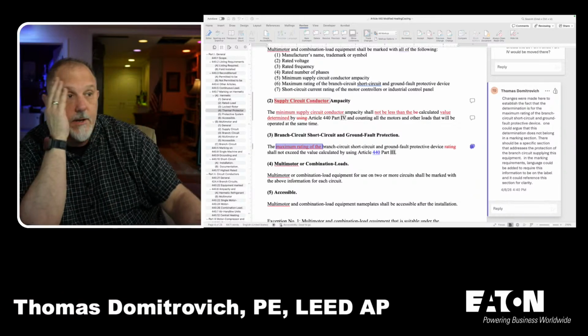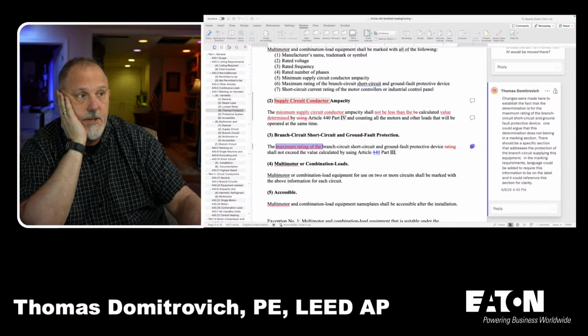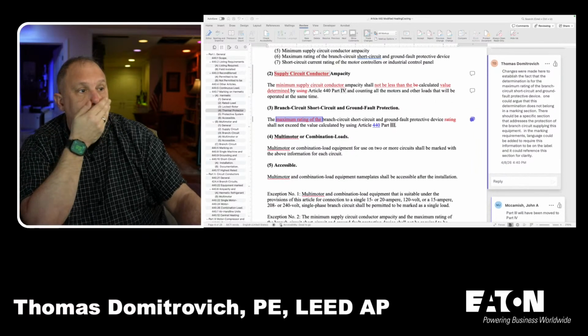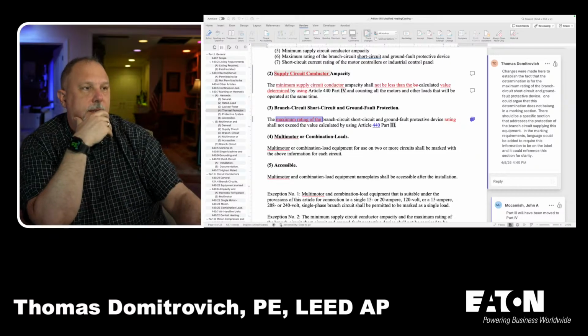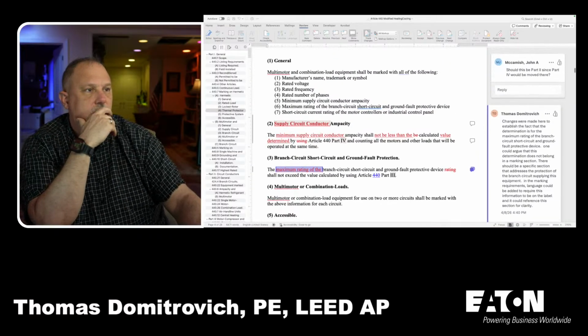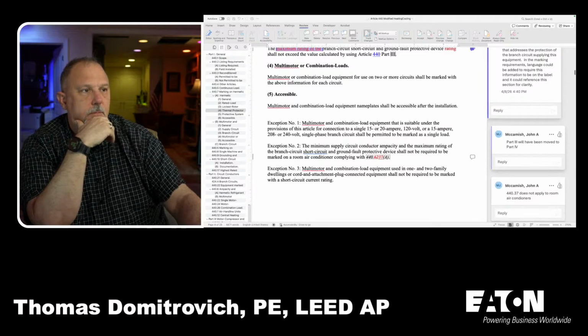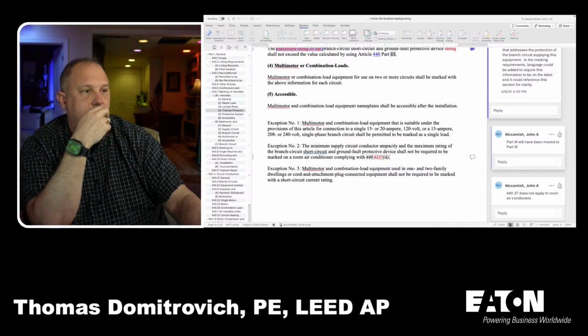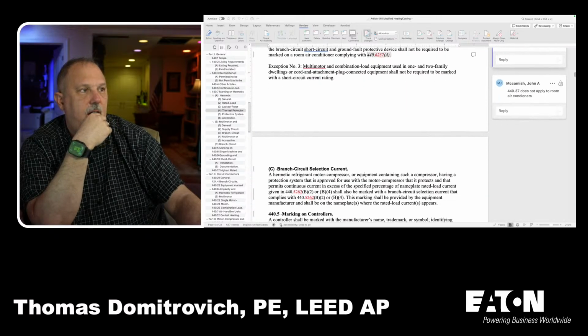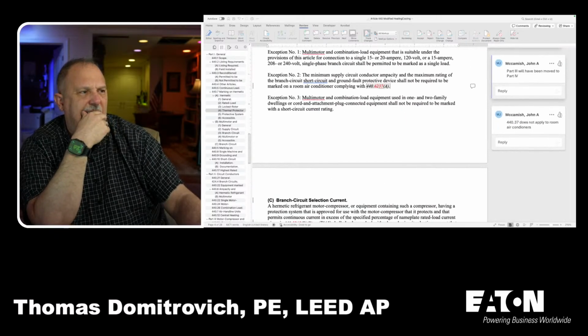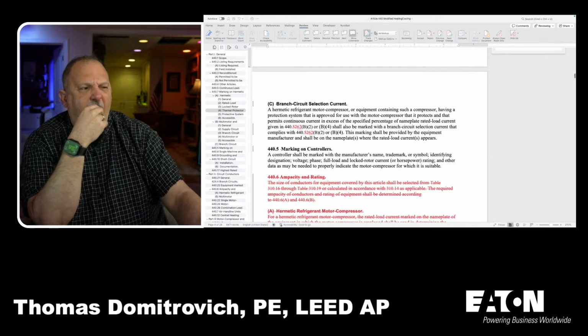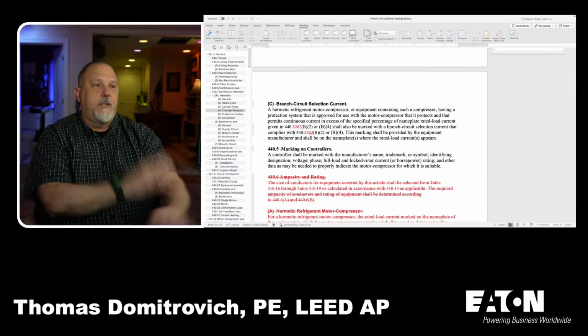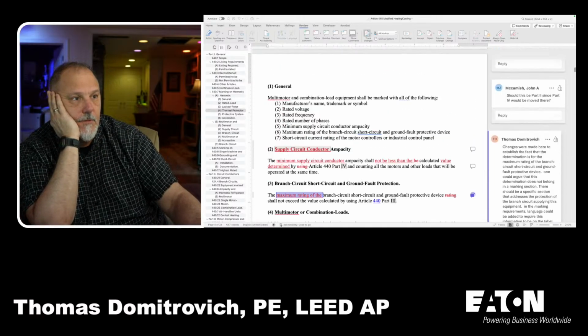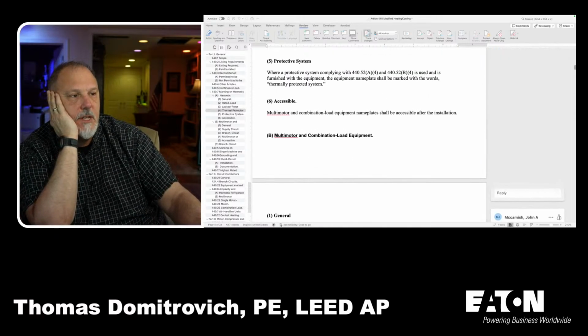All right, so we are combining two articles, Alan. You came in at the right time. All right, so we had that. We had the ampacity. Okay, accessible. Motor nameplates shall be accessible after the installation. So that's fine. And there's 3 exceptions. Branch circuit selection current. That's another C. Oh no, you're fine. So B is multi-motor.